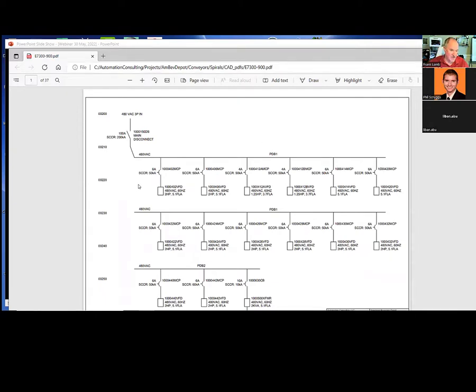This is how you can do a tentative layout and figure out sizing for everything. A lot of this is for safety—you want to make sure your short circuit interrupting ratings are high enough. This circuit breaker can interrupt 50,000 amps, so you want to pick components that can handle all this current.